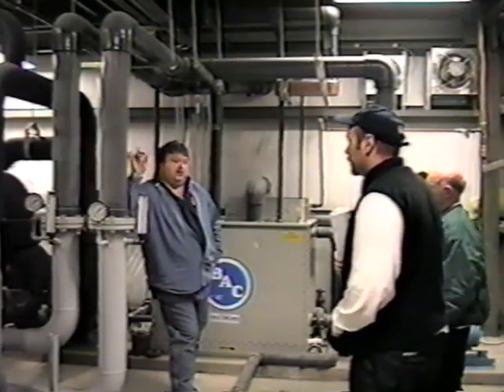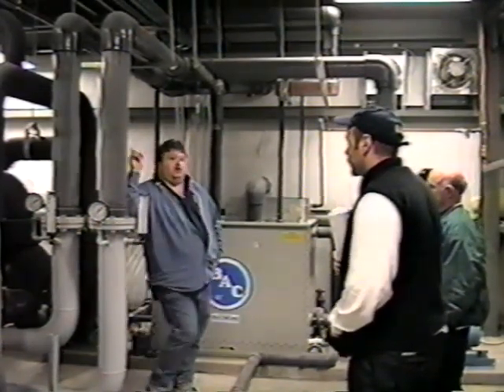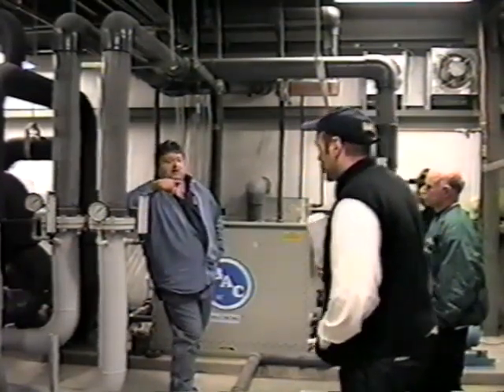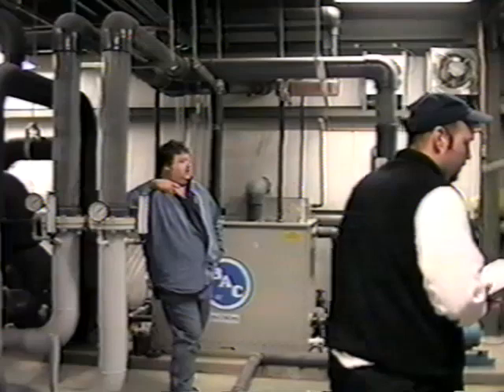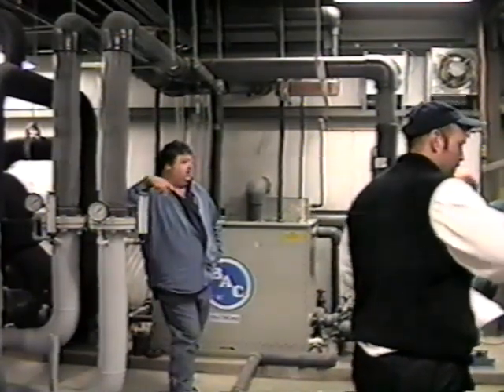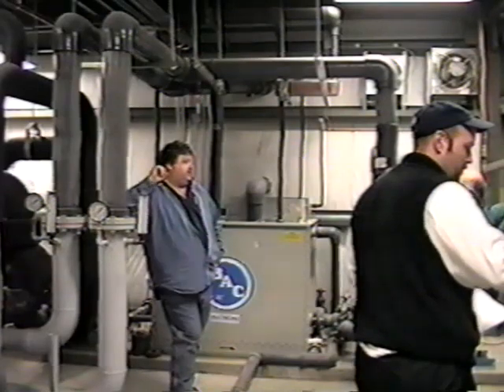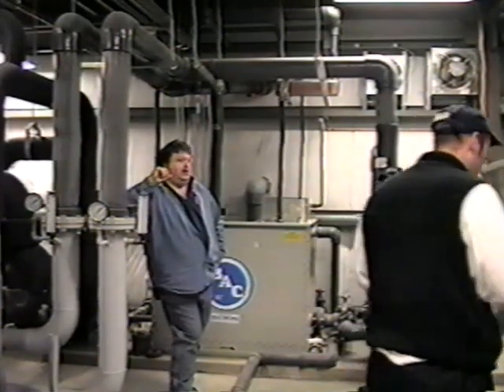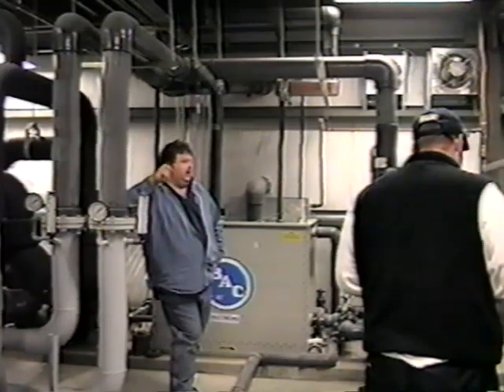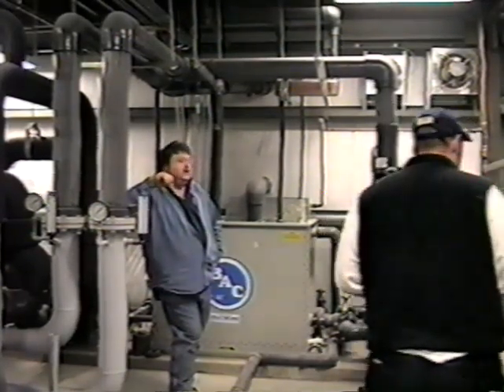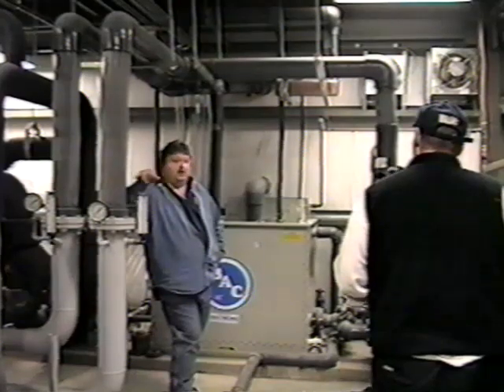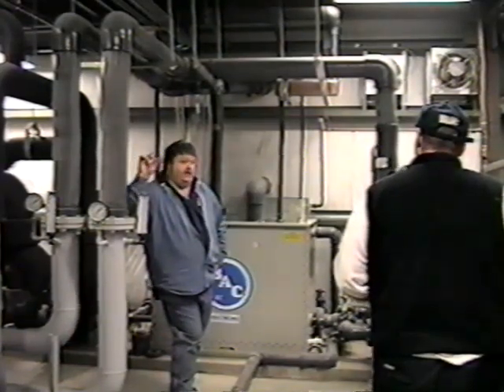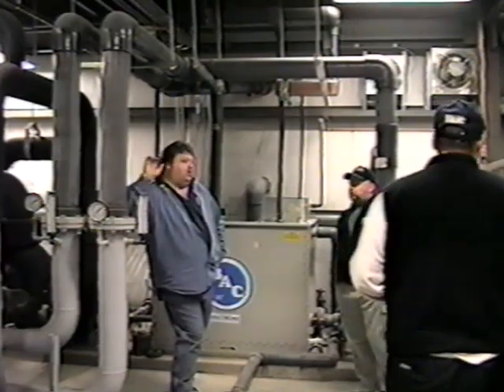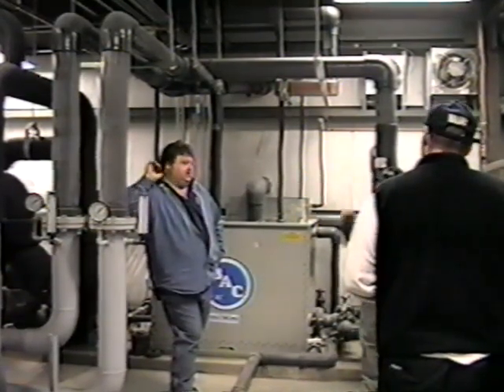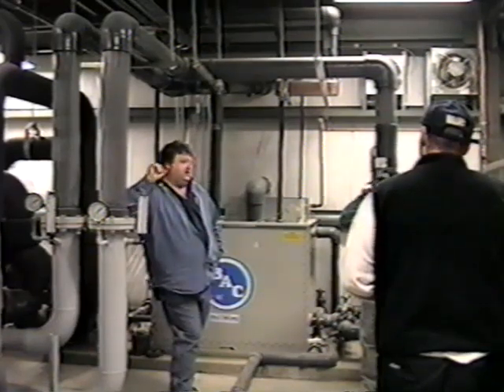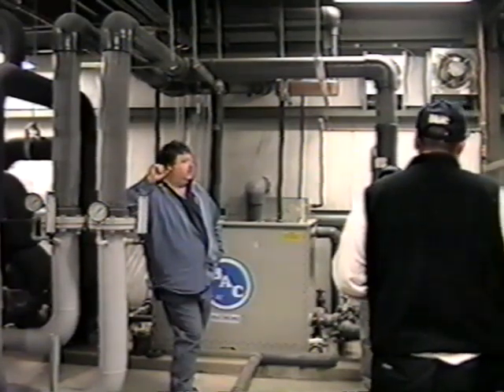Because these sensors are only good for so long, and we'll have to go through the paperwork on that, and you should come up with a schedule, let's say every 2 years, regardless, to replace the sensors. They have a lifetime on them. There are little heater elements in them, and the heaters go, and they get contaminated. If you have a leak that's large enough, a vent line leak will carry oil with it, and once the sensor has got that oil in it, you have to replace it. So that's good.